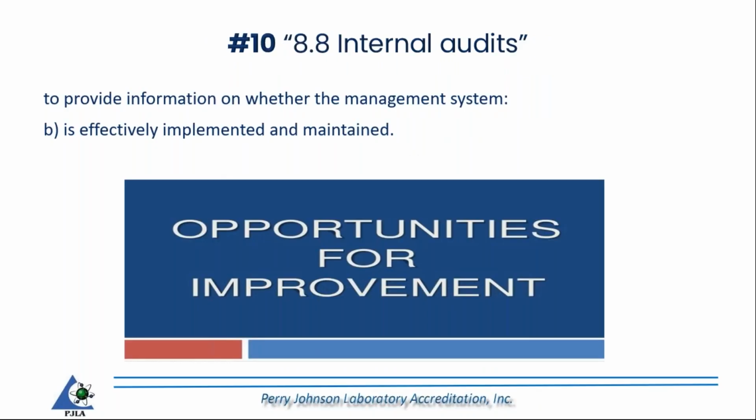So let me go back here before we get into the next area. The one thing with the internal audit, it has to support that the internal audit is looking at all the applicable requirements. Often I'll see perhaps a cross-reference checklist that has all the applicable requirements of the standards. So speaking on my behalf, yes, I have written nonconformances because the internal audit that was presented may not have provided evidence that all applicable requirements of the standard ISO/IEC 17025:2017 were subjected to the audit.